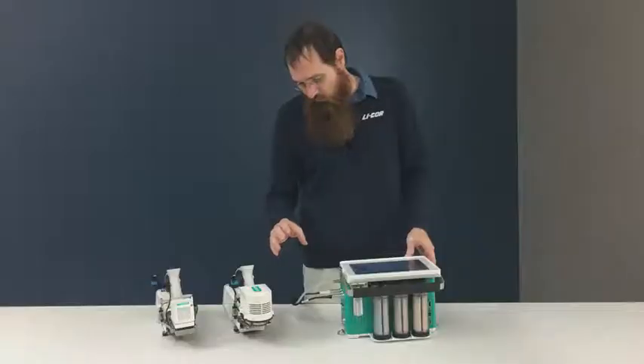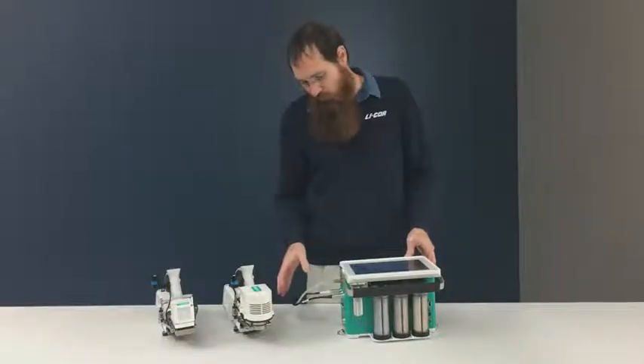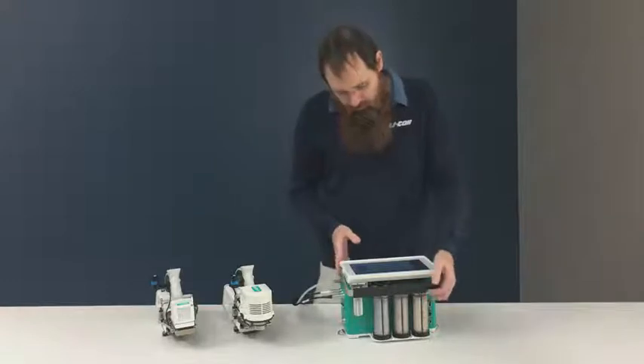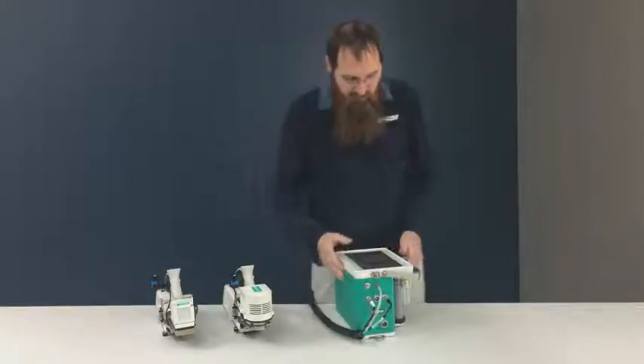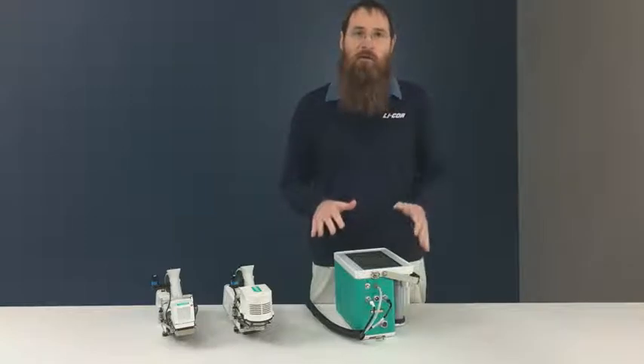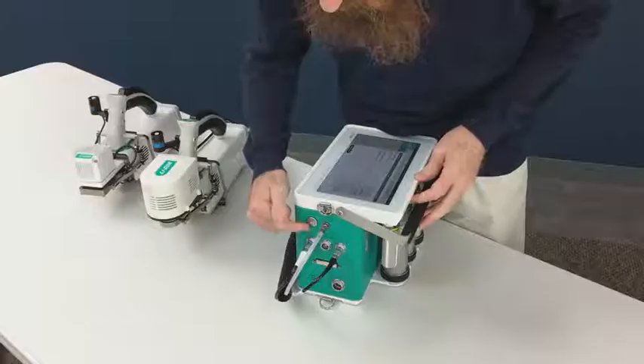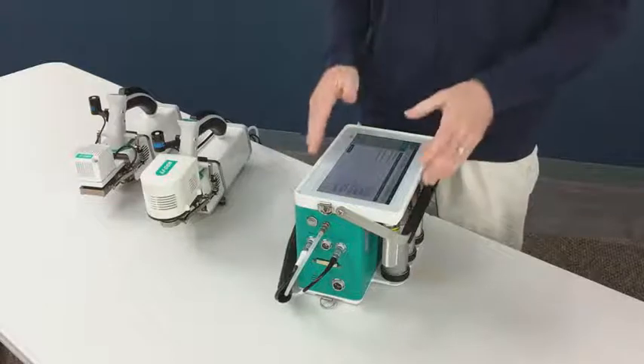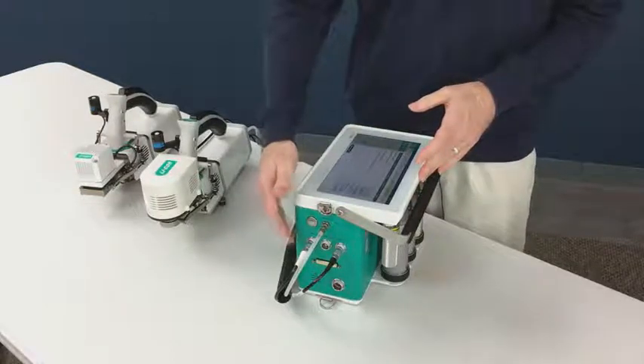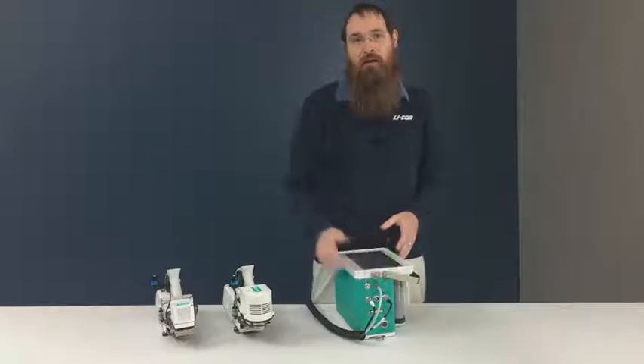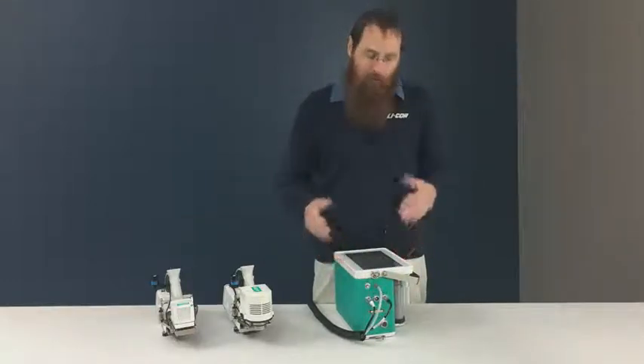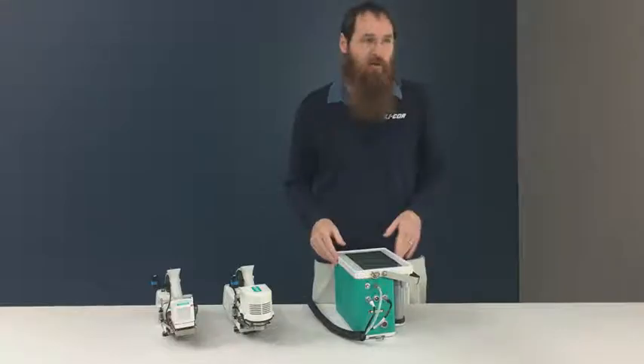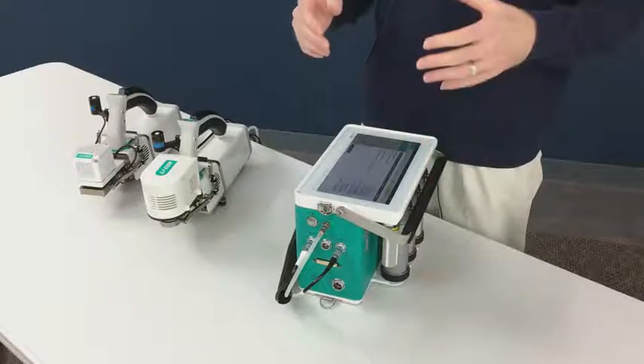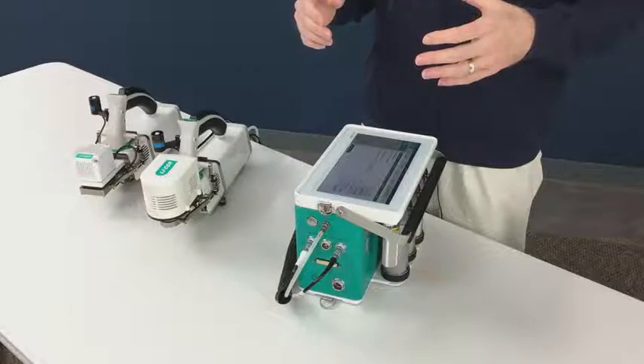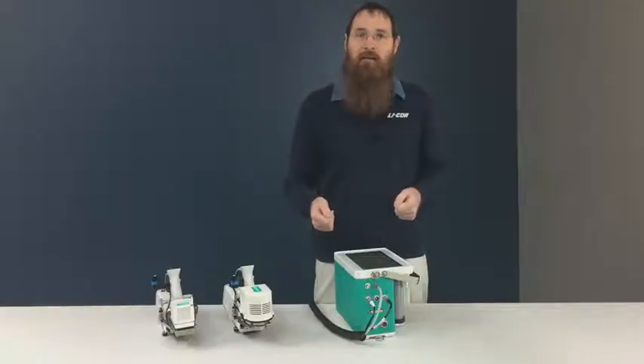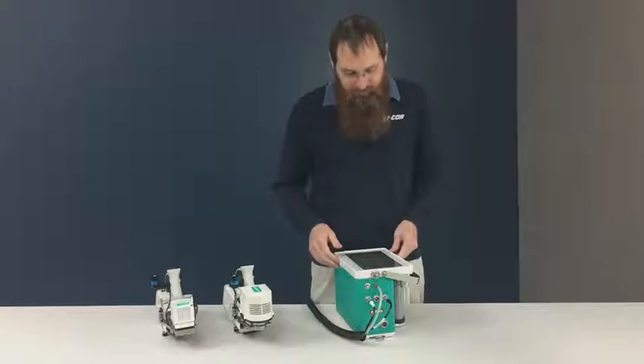One of these cables exists for the fluorometer, and one exists for the sensor head. The fact that everything is Ethernet lets us do some cool stuff with the instrument. Notice the ports on the side of the console are labeled head 1 and head 2. Because they're Ethernet with power, they're all pretty much the same—you plug something in, it figures out what's there, and if a connector fits and you plug it in, it'll work.